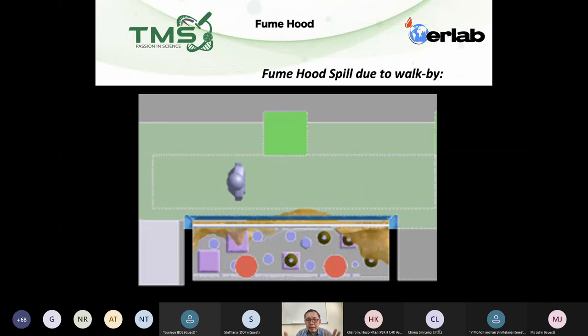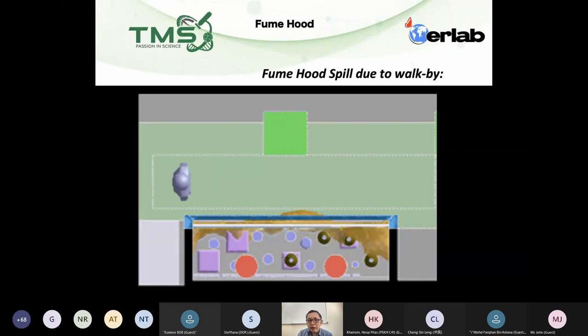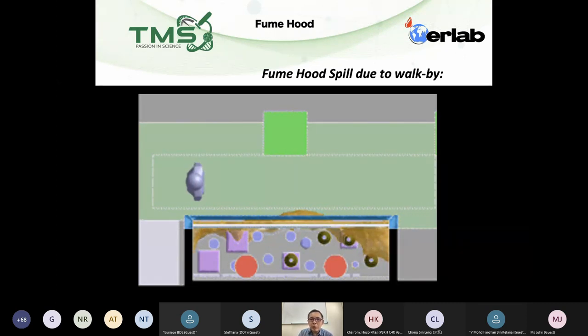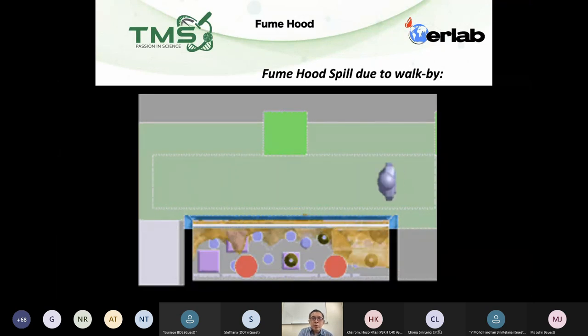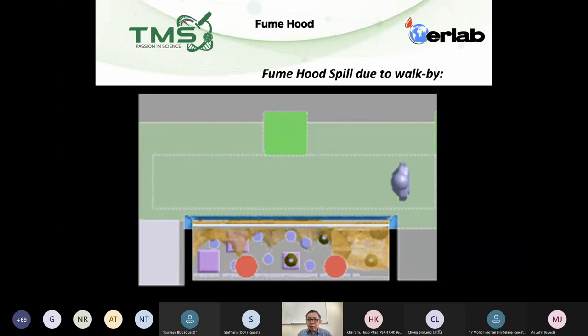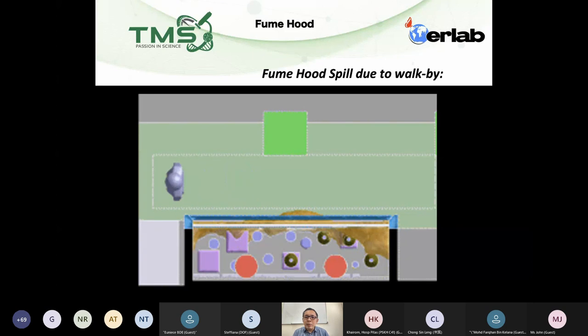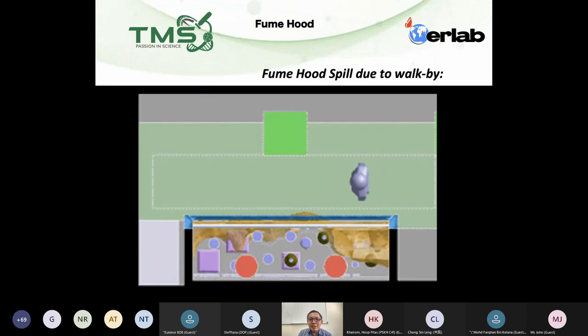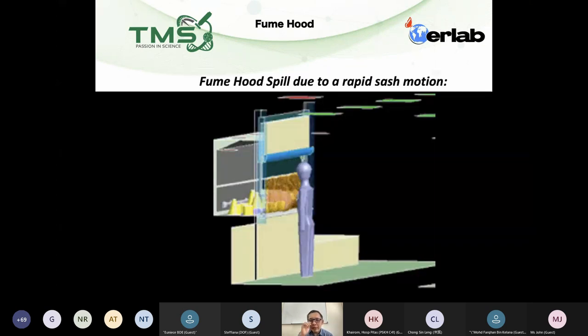When you have 0.5 m/s, minor changes in room pressure won't cause the chemical to leak out. However, there are two scenarios to avoid: first, do not run across your fume hood when chemicals are present. Moving swiftly across the hood creates an aerodynamic effect — a vacuum — that draws the chemical out and causes it to leak from the fume hood.